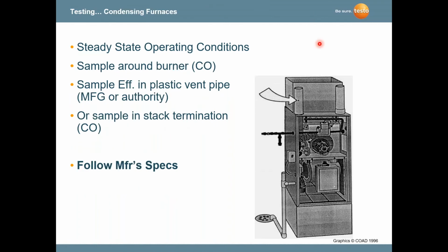Here's an atmospheric warm air furnace. Again, where you're going into the heat exchanger tubes, checking CO around the burner area, check fuel pressure, check carbon monoxide, again, not only in the flue gases, but also in the area of the combustion zone. Here's a condensing furnace here, going out into the stack for combustion efficiency, sample around the burner for carbon monoxide. Sometimes you can go into the stack termination if you're doing carbon monoxide measurement, but when you're doing combustion efficiency, you need to be closer to the combustion process.